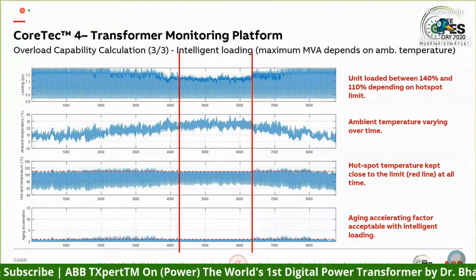Another use case: an aluminum smelter hired us to supply a solution to increase the capacity of their installation by 15%. They wanted to retrofit their existing transformers and get a payback period of 3 years. So what we did was first go and do a feasibility study based on the condition of the transformer and the risk associated with the equipment. Some minor repairs were needed, and then we decided to install the CoreTec 4 and the DGA device.